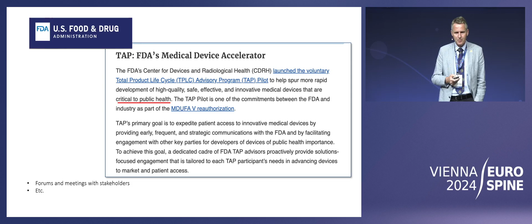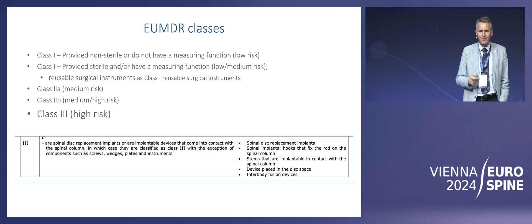Then there's the classification in the EU MDR. In our case, if you look at spine, it's mostly invasive devices, so implants, but it can be instruments as well. And even a software app falls under the EU MDR. Surprisingly, maybe Michel, you can explain, if you look at the table from the regulation, all spinal implants are class 3, because it says at the top that spinal implants, hooks that fix the rod to the spinal column, are class 3. But I know that hooks and pedicle screws are sometimes 2B, so I don't even know what that is. Anyway, most spine implants are high risk, which means the level of evidence needed is high.